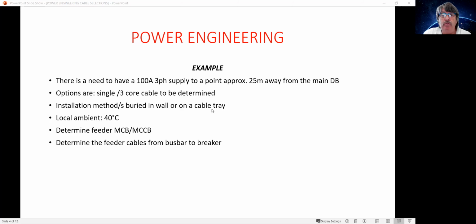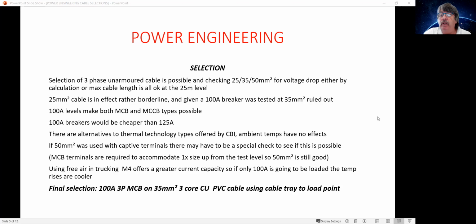I just want to go back to the selection. When we had a look at the selection, we could choose anything from a 25, 35, and 50 mil cable. We looked at that. If you look at the volt drop at 25 meters, you can do that either by the calculation method, or you can look at the maximum length of cable, and you can see that all of those cables at 25 meters would be lower than the 5%. And there would be no need to worry about the volt drop at that point.